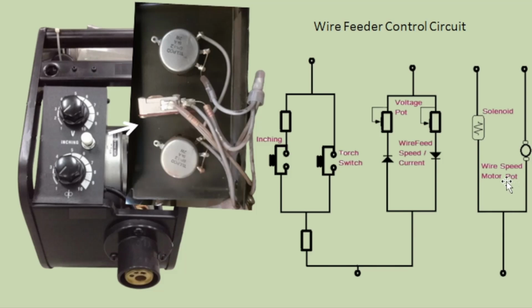Other control connections from control inputs are going to remote box and very much tricky. Torch and wire inch, both signals from the switches are used by a single wire. Two signals are differentiated by voltage drops. Voltage drops across resistive circuits are different for each switch. Torch signal will come from the torch by operator through euro connection. Single wire is also used for voltage and current signals from two potentiometers. Pulsating waveform from the wire is segregated by diodes for positive and negative cycle.